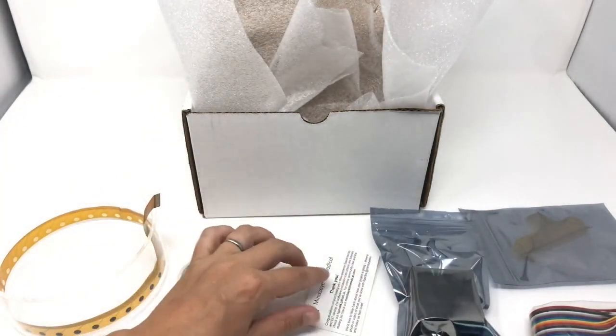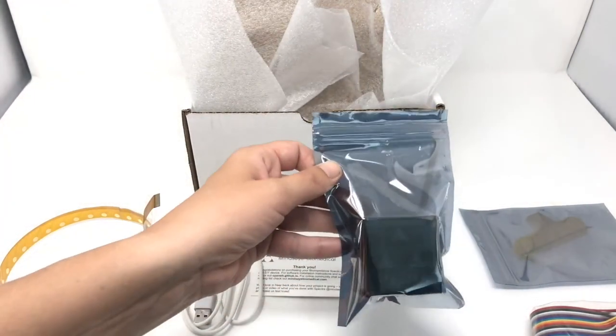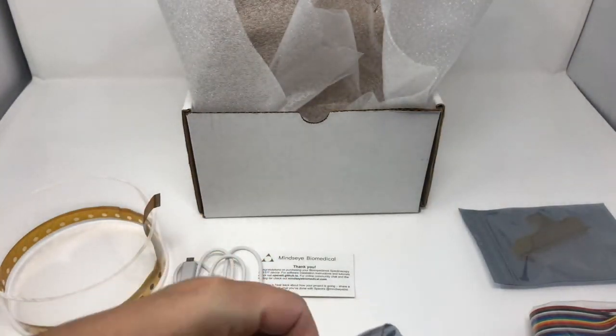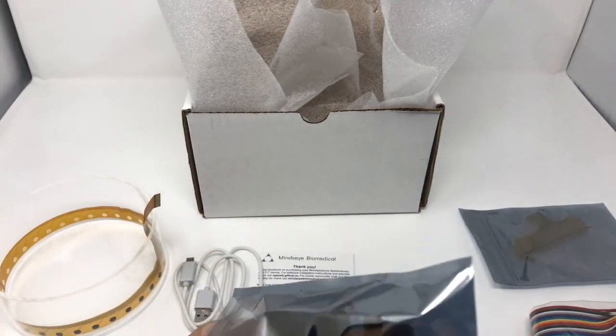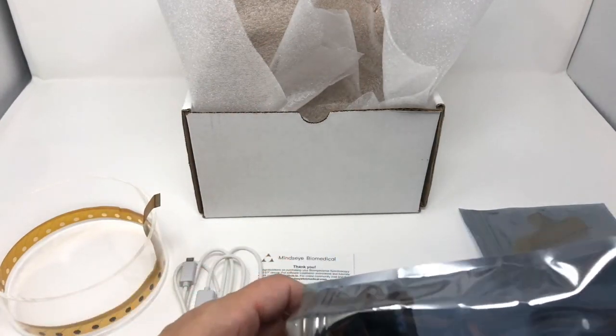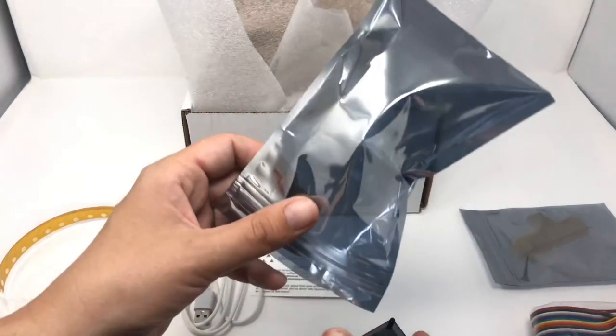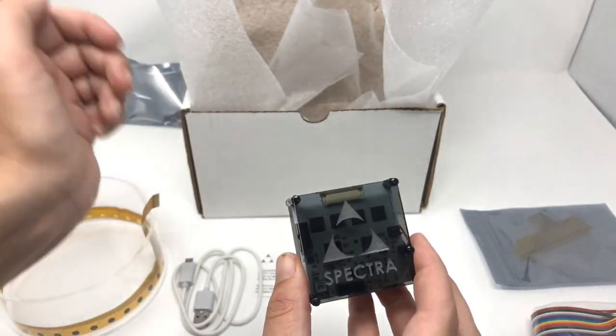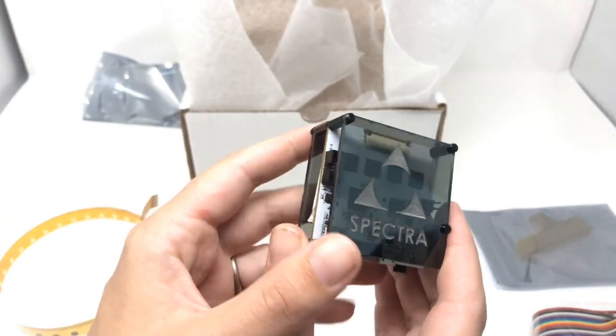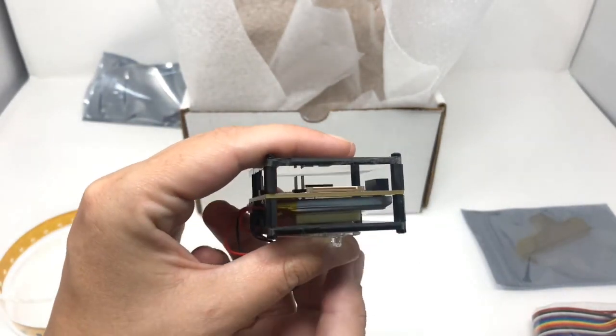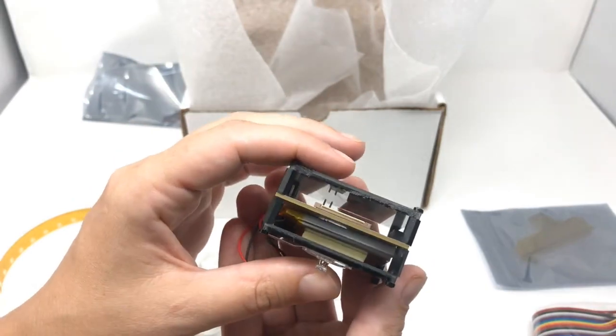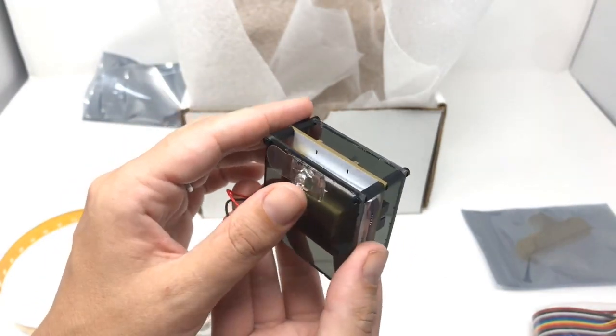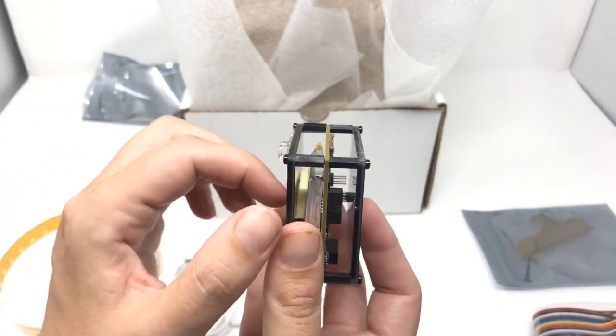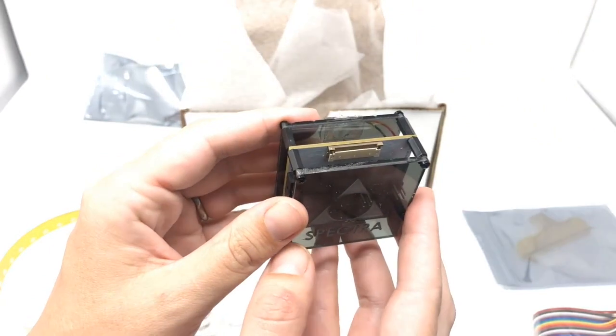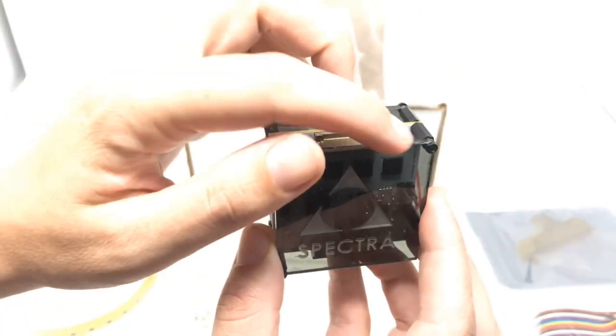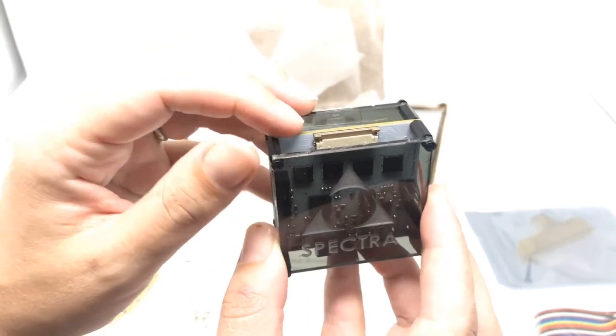Once you've taken everything out and made sure that you've got everything you expected to, we're going to set up a Spectra device by plugging it into the flex electrode array on the tank. So let's just get it out of an anti-static bag. There we go. So here's a Spectra. This one I've actually already put a battery in. I'm not sending batteries around because it makes postage more tricky, but you can get one yourself. There's a little hook here, you'll notice. And most of all, there is this FPC connector right at the top here, which we're going to focus on.